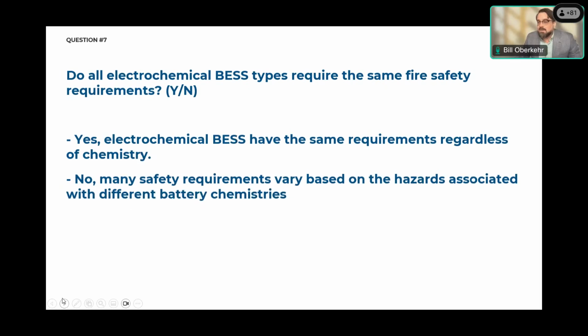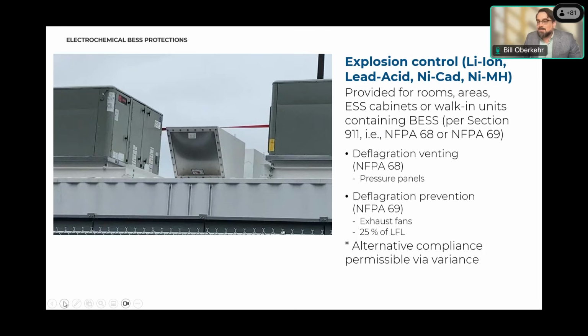No, many safety requirements vary based on the hazards associated with each. Explosion control is not something that we have for all types, but it is something that applies to lithium ion. We have two main NFPA standards that apply to explosion control. That's NFPA 68, which is the deflagration venting, which are those vents that pop up when there is a critical mass of gas built up inside the container, and NFPA 69, which is explosion prevention.